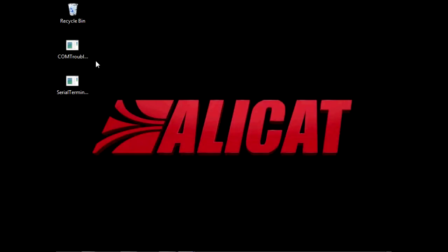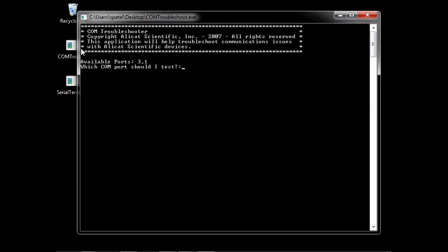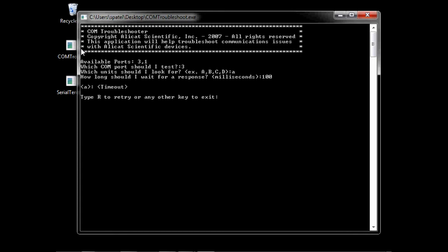Once executed, you will be presented with a listing of available ports by number. Then, simply enter which port number you'd like to test, the unit ID of the Alicat device, and a wait time in milliseconds. 100 milliseconds is a good starting point.